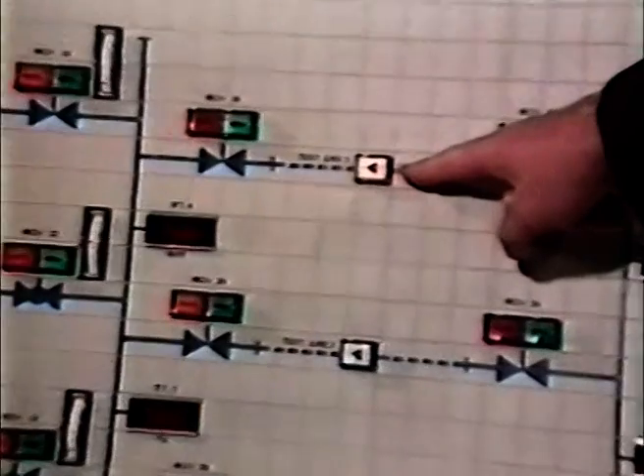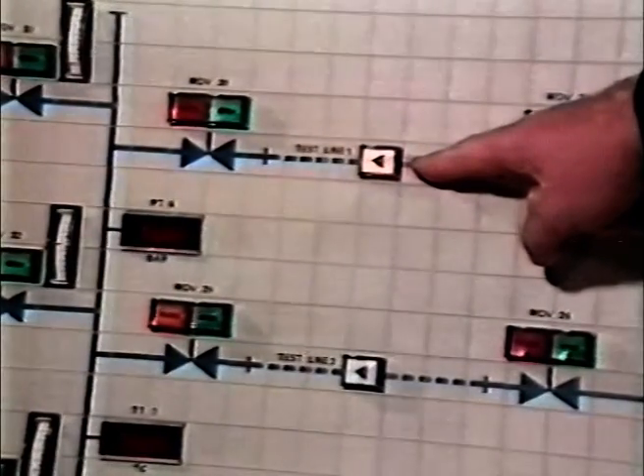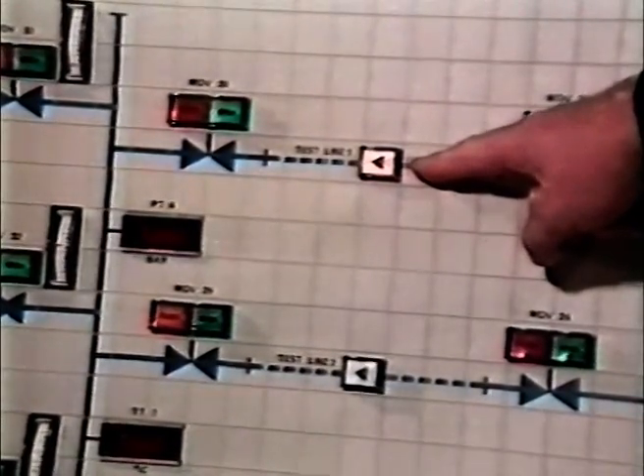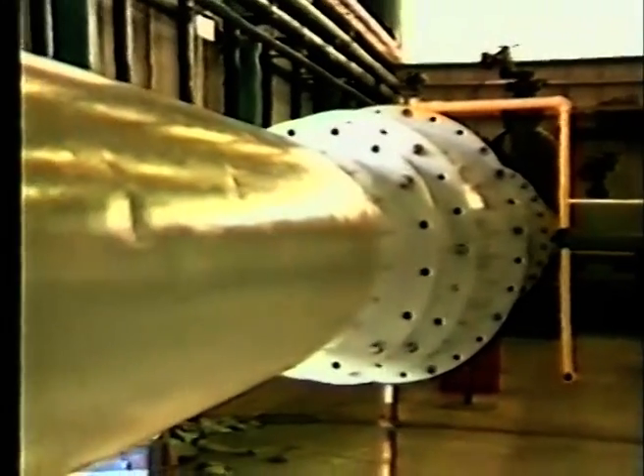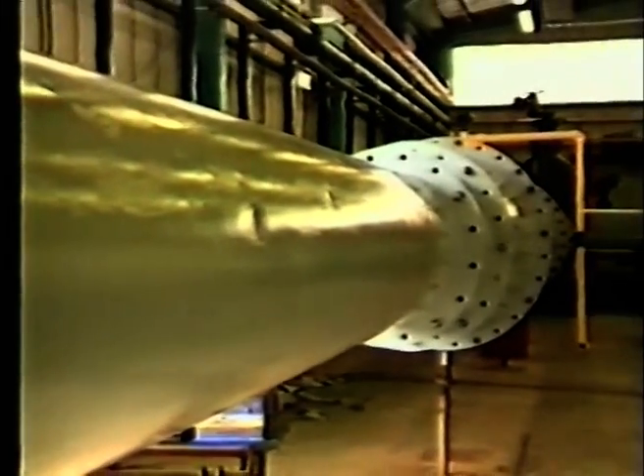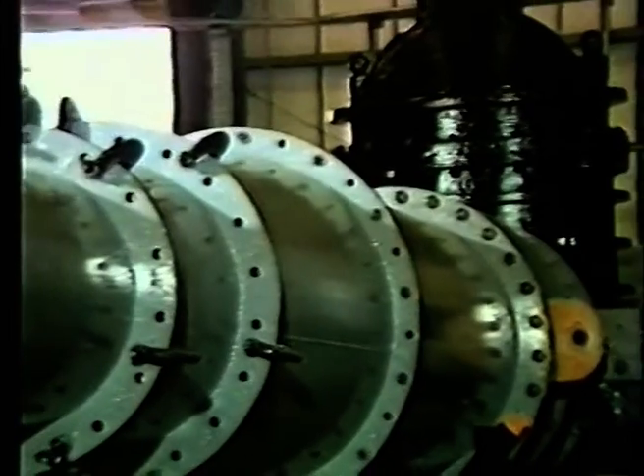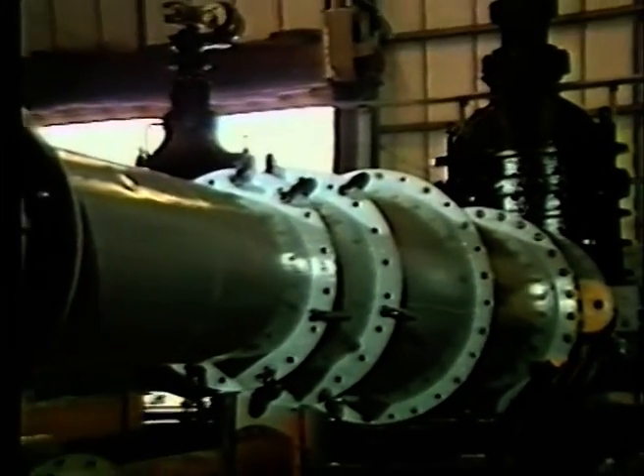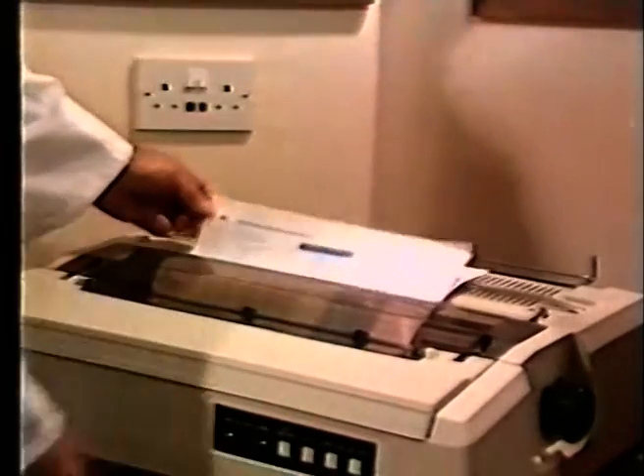Now we've discussed the basic principles, let's take a look at a typical meter under test. The first step is to fill the system and to run the plant up to its desired flow condition, and to maintain that flow rate until the air is purged from the system. Tests can be conducted either short-term or continuously. A typical production calibration for a Kent Veriflux flow meter, for example, would consist of 5 runs, and the computer prints out the results on this official certificate.